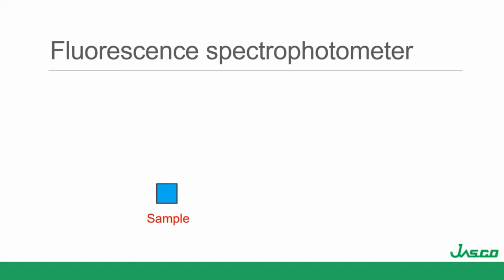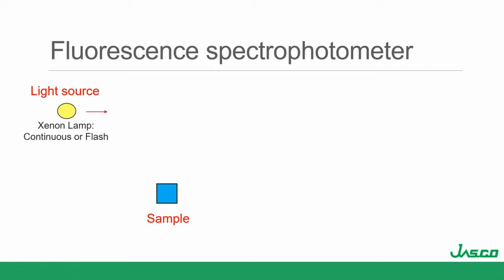We'll work in solutions — that's an easy start. What do I need? Well, Beer's Law says fluorescence is proportional to the intensity of the excitation light, so I need a light source — it's usually a xenon lamp, either continuous or flash lamp. Continuous has the added advantage of significantly greater output, and remember: more light in, more light out. You get a lot more sensitivity with the continuous sources.